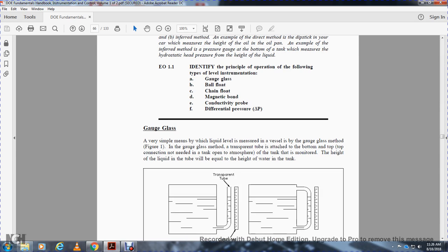Gauge glass is very simple. With the gauge glass method, the liquid level in the vessel is monitored with a transparent tube attached at the bottom and the top of the tank. The connection is open into the atmosphere over the tank. The height of the liquid in the tube will equal the height of the water in the tank.